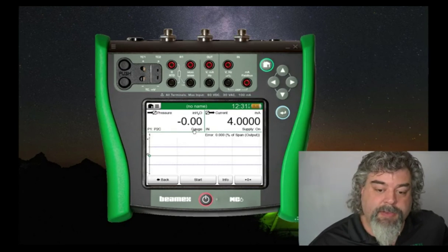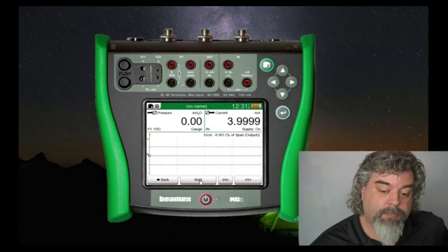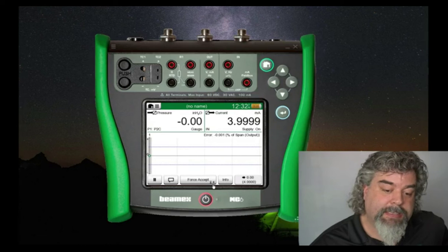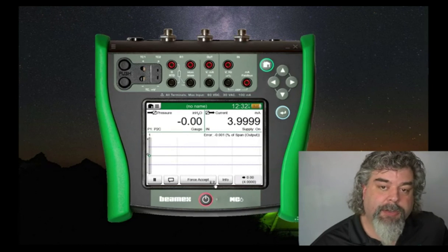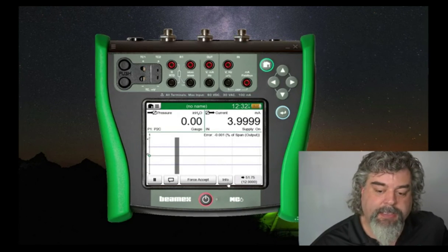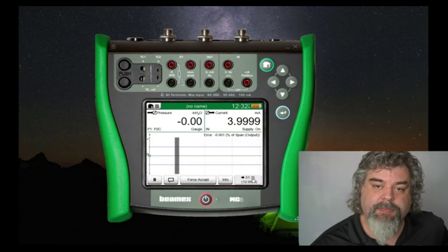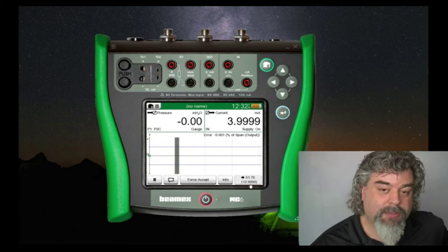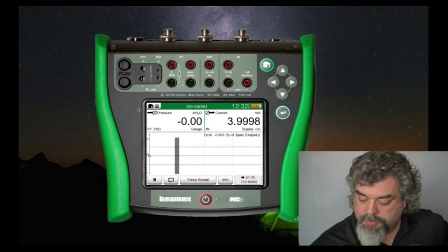So my pressure pump is vented. We have 0 in here. There's no need to do a re-zero. I could, but let me hit start. Now we're in our gray bar. We're in our target area, so we have a 5-second countdown. Now the next test point is 51.75 inches of water in and 12 milliamps out. So let's do that.